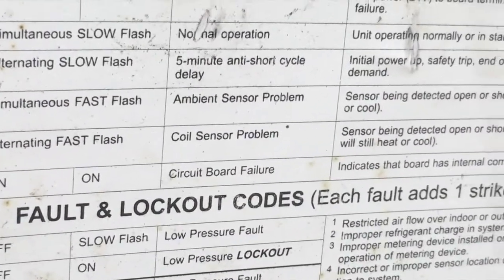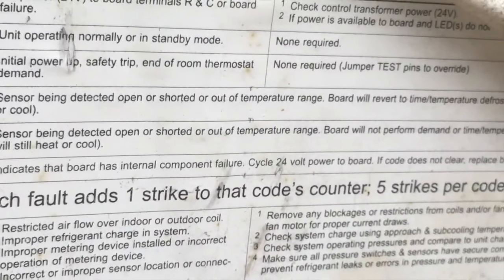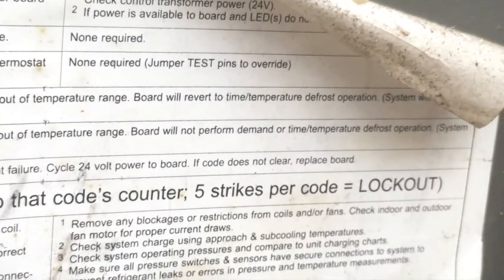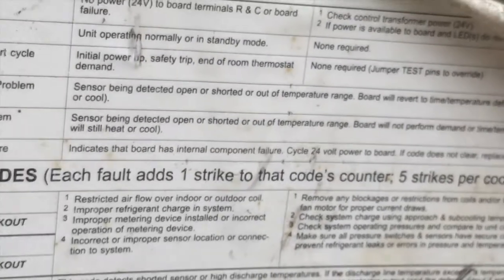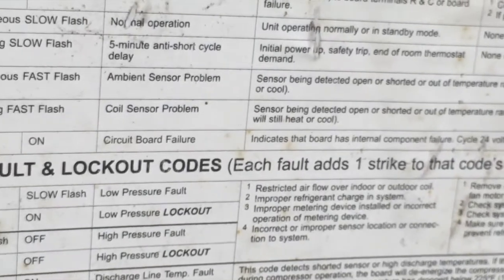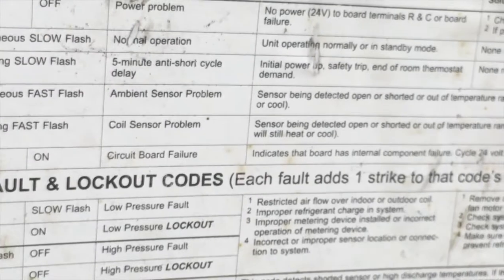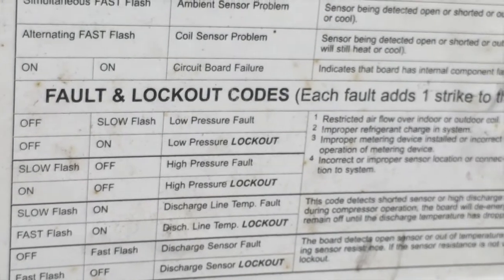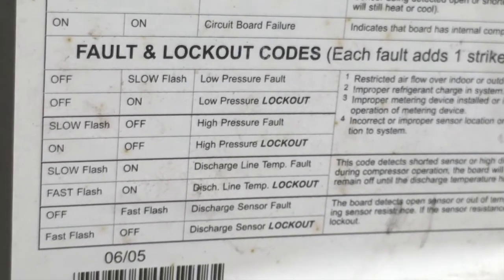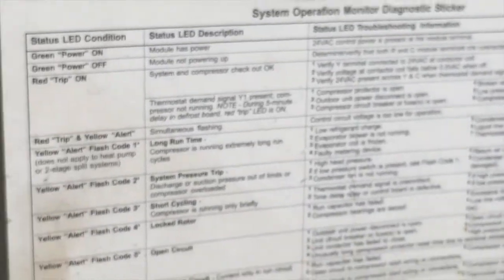If you see alternating fast flash: coil sensor problem — sensor being detected open or shorted, or out of temperature range. Board will not perform demand or time/temperature defrost operation. These are some things you can look at. If you're getting that issue, look at the sensor, test it, see if it's bad before you go calling out an AC guy — only if you feel comfortable doing so. There's also fault codes for a slow flash on low pressure lockout and so on, that could lead you to issues you may be able to fix yourself.